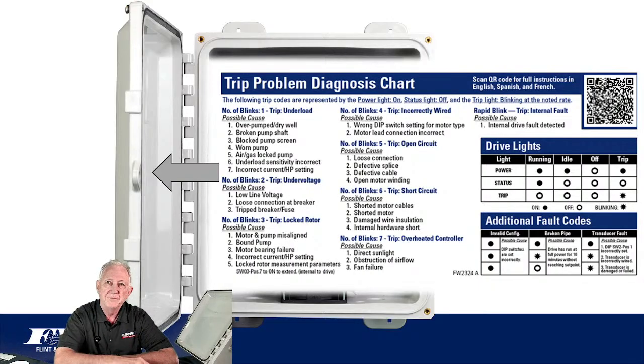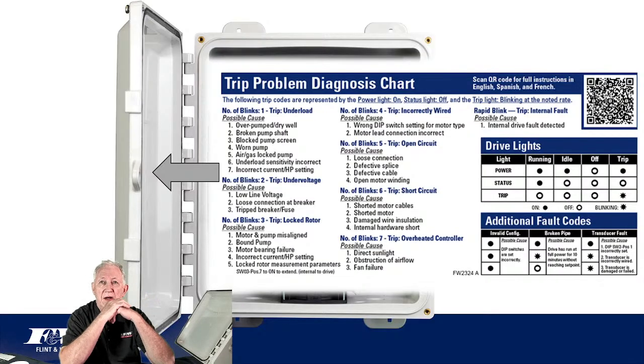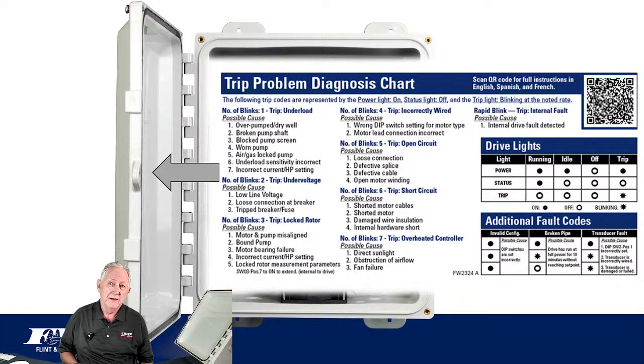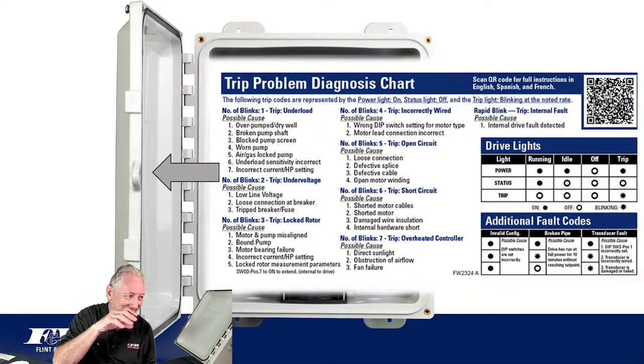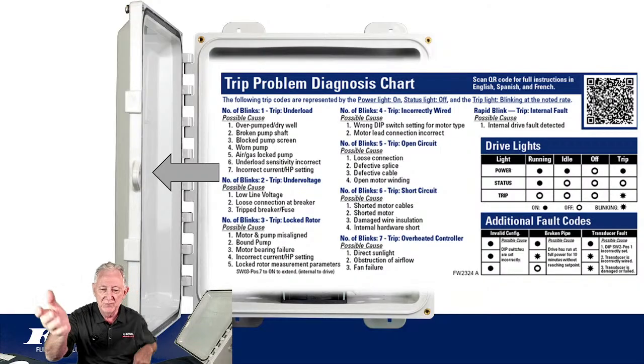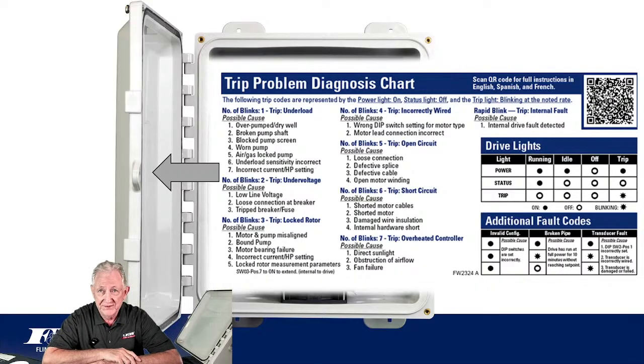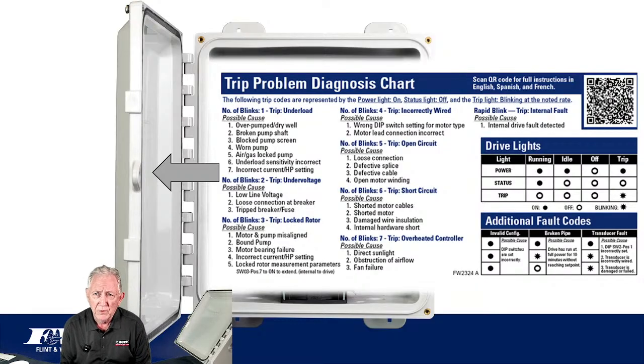When we look at that label, there's really everything we're going to need to know based on the status lights themselves. Let me try to clarify this just a second. When they're blinking, particularly the red one, which is your trip light, it's going to blink in sequence. It's either a sequence of 2 blinks, or 3, or 4, or 5 blinks, but they're going to be sequential. Inside this cover is that chart, and that chart has the diagnostics on it. So you look at the number of blinks that light's given you, and then you reference that on this chart. You can see up there, I hope you can see this on your screen, that this will indicate an underload or an under voltage, a trip, locked rotor, and so forth. But that chart's going to be right on the inside cover of the drive.